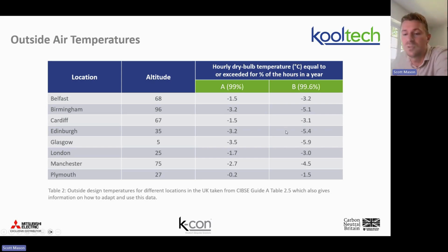We've got products in our range which, in the south of the UK, I would describe as a hot water product. So it can do heat or it can do hot water, because it can deliver 65 degrees centigrade at these design ambients. So I can make potable hot water. But when you get down to like -5, for example, our colleagues up in Scotland would use that product significantly less for hot water because we can't get over 60 degrees. So if we do use it for hot water, we have to incorporate things like pasteurization regimes, etc. And actually, there are probably better products suited at that point in time. So the outside design temperature changes significantly what products in our range are actually available.